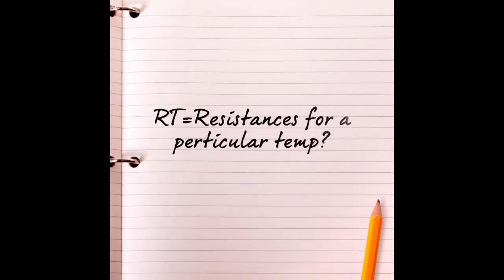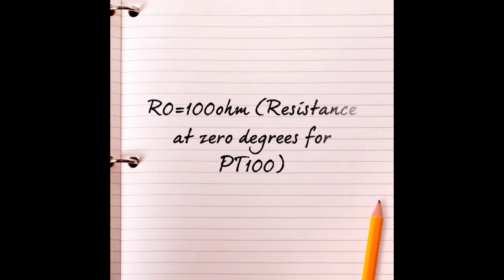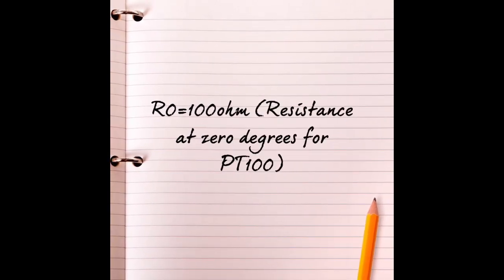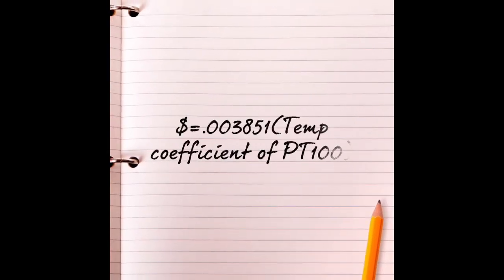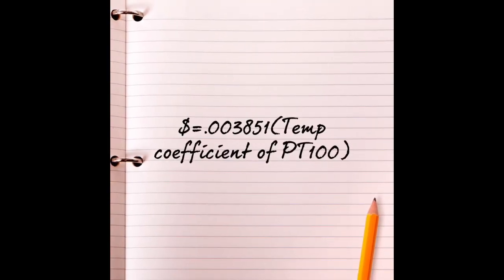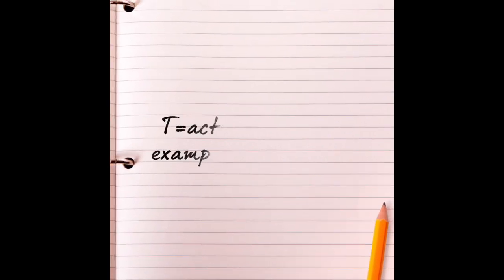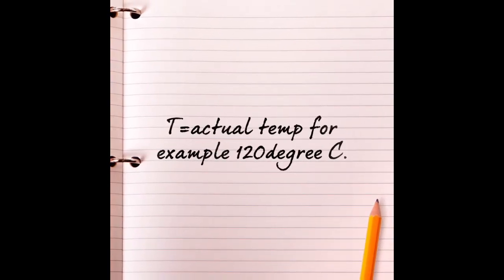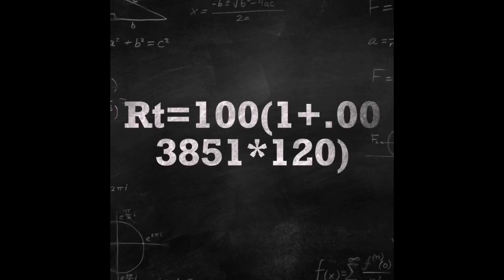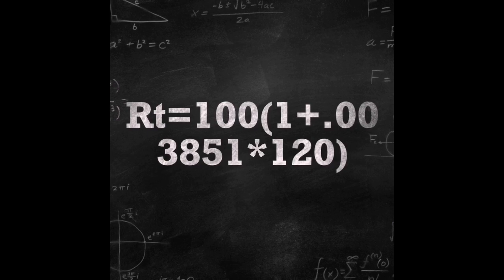Where RT is resistance for a particular temperature, R0 is resistance at 0 degrees Celsius (100 ohms), alpha is 0.003851 (temperature coefficient of PT100), and T is actual temperature. We are going to use 120 degrees for this example.